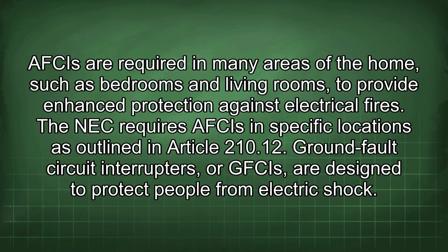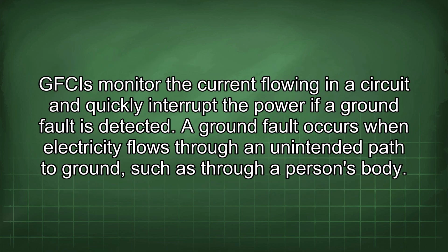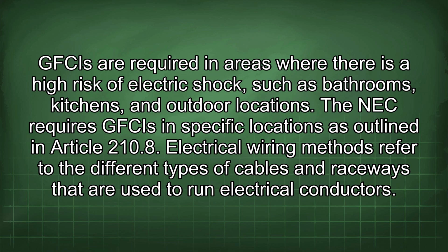Ground fault circuit interrupters, or GFCIs, are designed to protect people from electric shock. GFCIs monitor the current flowing in a circuit and quickly interrupt the power if a ground fault is detected. A ground fault occurs when electricity flows through an unintended path to ground, such as through a person's body. GFCIs are required in areas where there is a high risk of electric shock, such as bathrooms, kitchens, and outdoor locations. The NEC requires GFCIs in specific locations as outlined in Article 210.8.